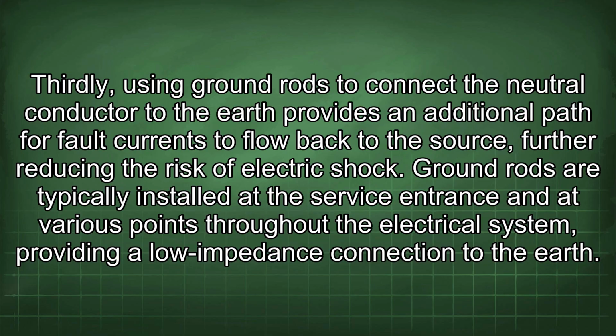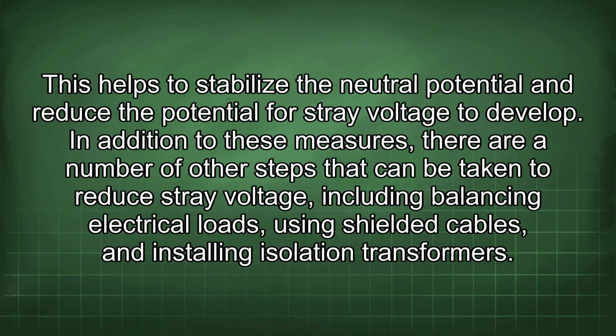Thirdly, using ground rods to connect the neutral conductor to the earth provides an additional path for fault currents to flow back to the source, further reducing the risk of electric shock. Ground rods are typically installed at the service entrance and at various points throughout the electrical system, providing a low impedance connection to the earth. This helps to stabilize the neutral potential and reduce the potential for stray voltage to develop.